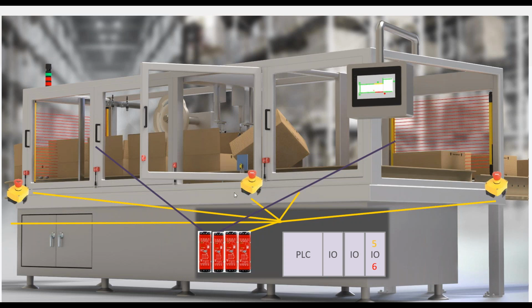And the reason I'm showing home run cables of each one of these E-stops back to the panel is, if you look up here on the HMI, this machine is displaying the status of each one of those E-stops. The way they're doing that is they'll run a cable back with the safety on-off wires plus an auxiliary wire to indicate back to the PLC which one is pressed. They do the same thing with the door switches. So they'll run a line for each one of the E-stops and each one of the door switches back to an I/O card on the PLC. Then they'll land each one of those auxiliary wires here, program the PLC so that it knows those inputs correspond to the E-stops or the door switches, and then send that information up to the HMI. The safety wires get tied to the relay to do the safe on-off.